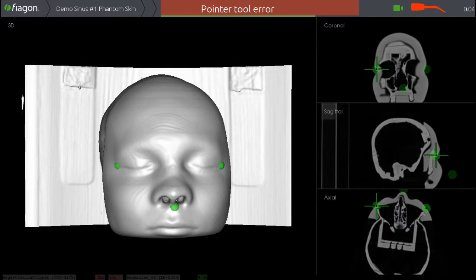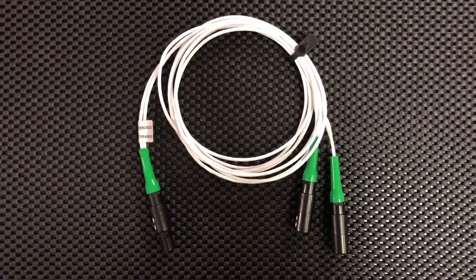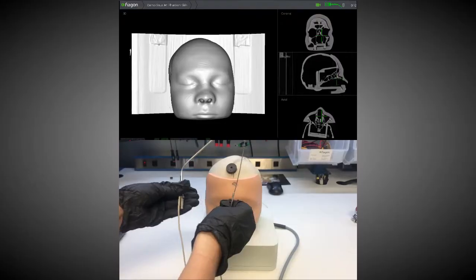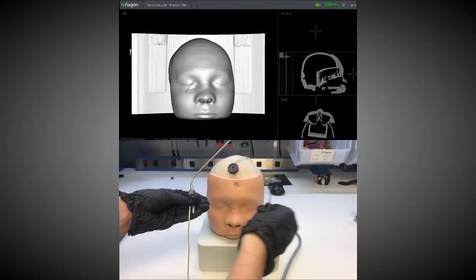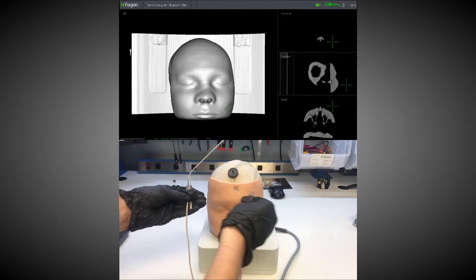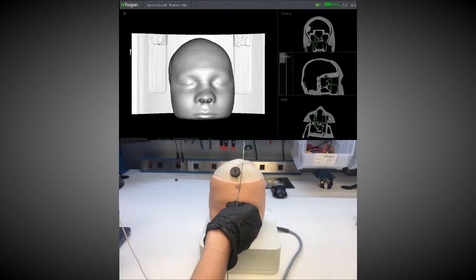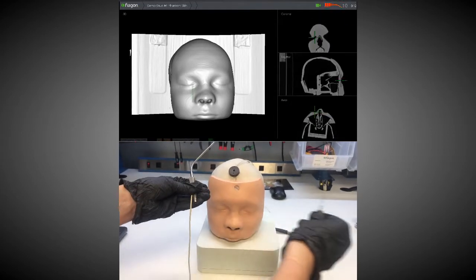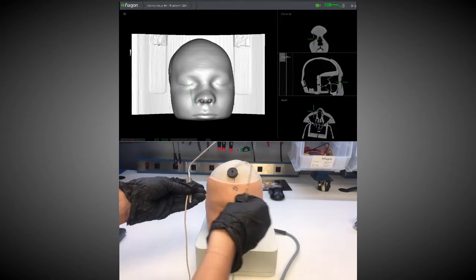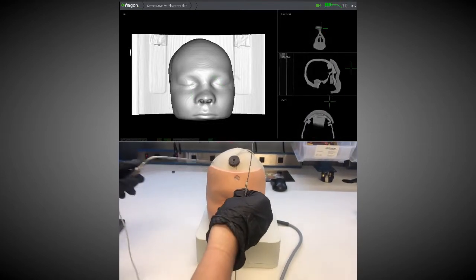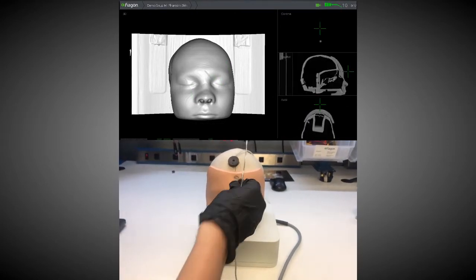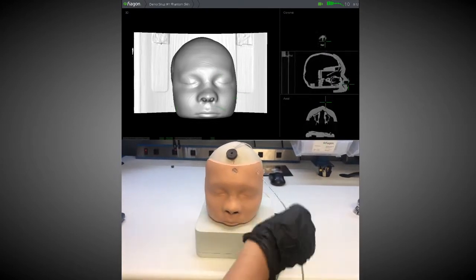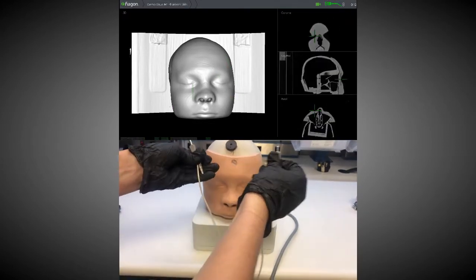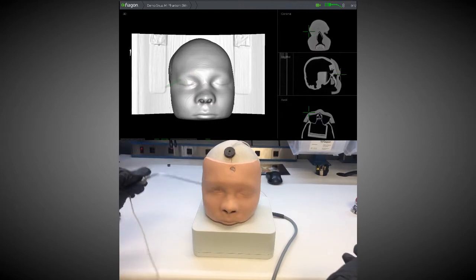Note, when 2 instruments are plugged into the system via the double instrument support cable, the first instrument that is brought into the electromagnetic field will be the instrument that is tracked. If a second instrument is brought into the field while the first instrument is still in the field, the system will not recognize the second instrument and thus will not track it. In order to track the second instrument, the user must remove the initial instrument from the electromagnetic field.